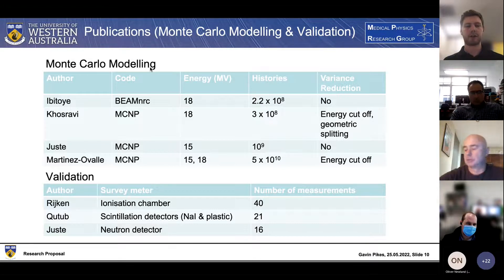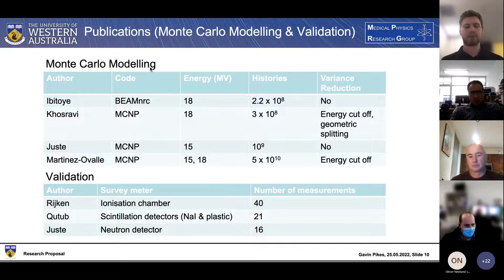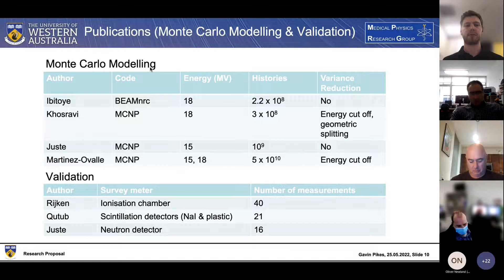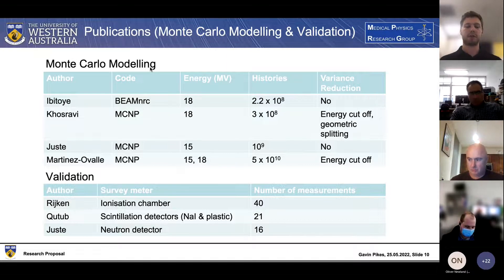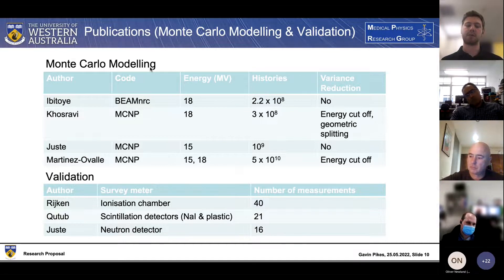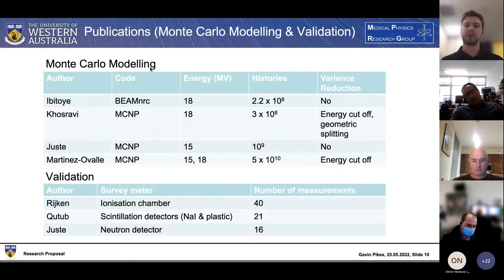In terms of validation, most Monte Carlo models are being validated against energy deposition measurements taken within the bunker. A number of different survey meters have been used, but the important bit is the number of measurements taken - most people are using between about 16 and 40 on average, which allows for quite a good comparison between the measured results and the simulated results.